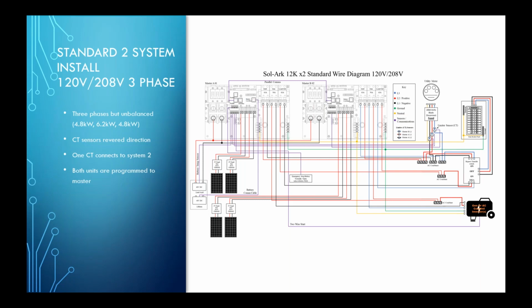Absolutely. So again, obviously the main difference here is that in a two system setup, it is an imbalanced 3-phase. So you do get all 3 phases in terms of output, but as you can see in the notes on the left, it is a 4.8, 6.2, and a 4.8. So it is what we call unbalanced in that sense. And then the biggest difference here is going to be the wiring.